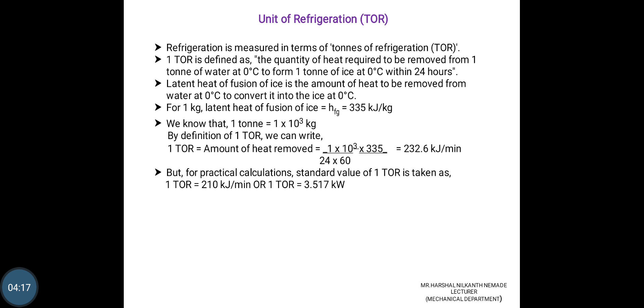For 1 kg, latent heat of fusion of ice is equal to hfg, which is 335 kilojoules per kg. We know that 1 ton is equal to 1 into 10 raised to 3 kg. By definition, 1 TOR is equal to the amount of heat removed, which is 1 into 10 raised to 3 multiplied by 335 divided by 24 into 60. You will get the answer 232.6 kilojoules per minute. But for practical calculation, the standard value of 1 TOR is taken as 210 kilojoules per minute, or 1 TOR is equal to 3.517 kilowatt.